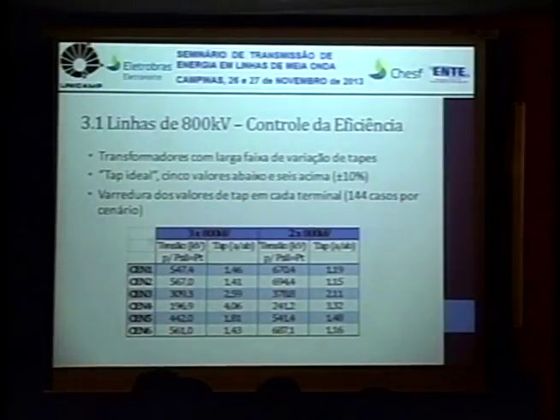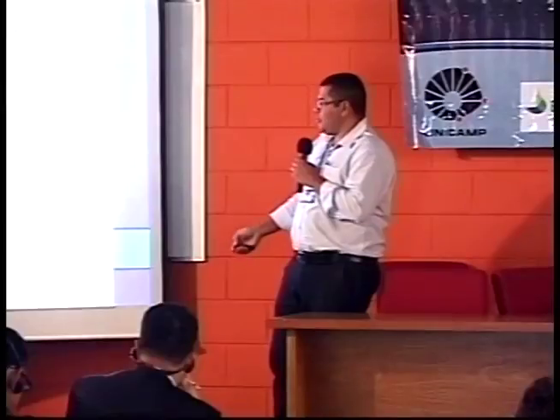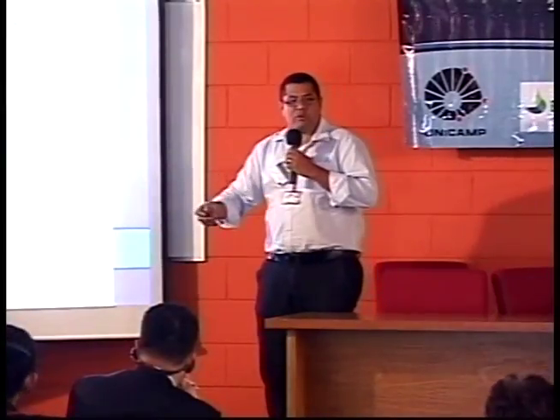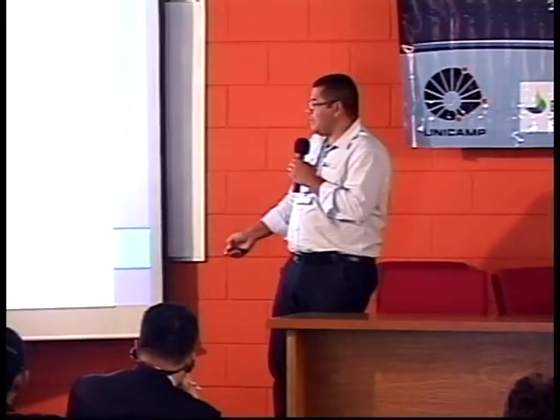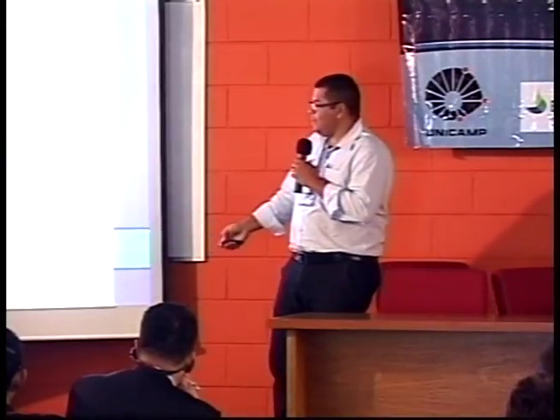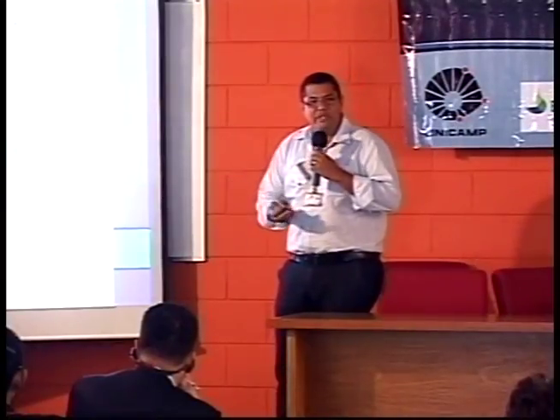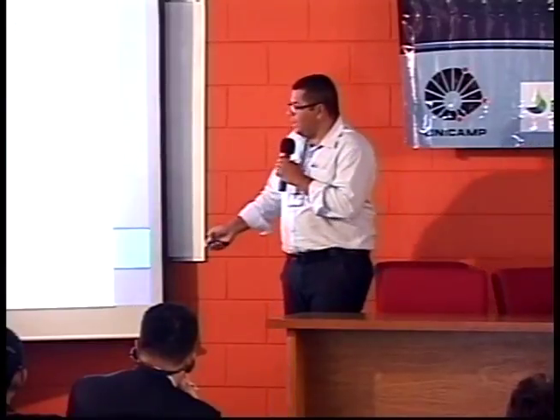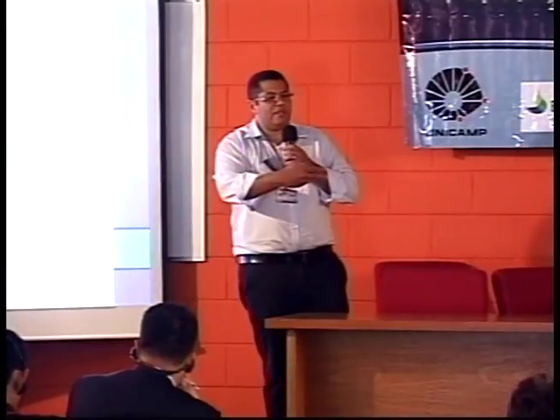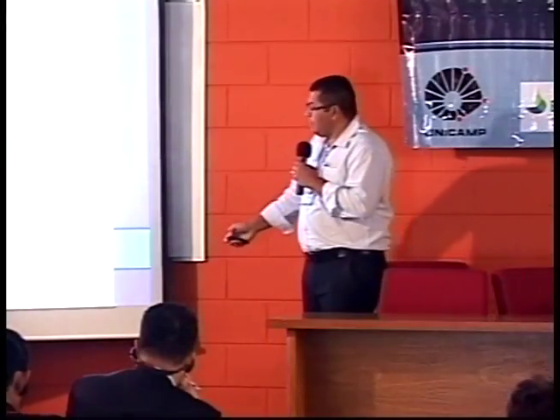So we do this. However, with this wide variation of tap, when I change the tap, I change the voltage, but I also affect the transmitted power. Because when we talk about conventional transformers, the tap is always close to 1 pu. A change in the tap is going to vary very little the active power transmitted in the line. In this case, when we are changing the tap a lot, when I change the tap, I change the transmitted power. So we always need to make consecutive adjustments around this ideal tap, so we can look for the point with minimal losses and maximizing the efficiency of the line. And so we can also ensure that reference power we are going to transmit in that scenario.